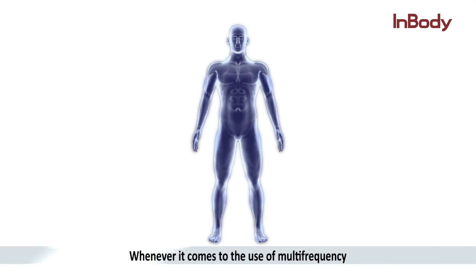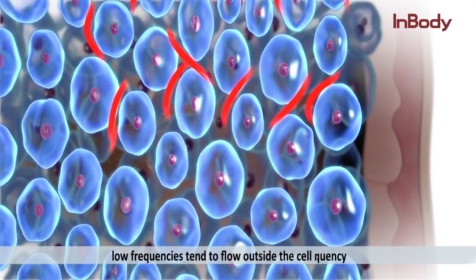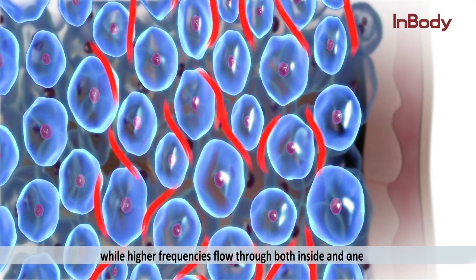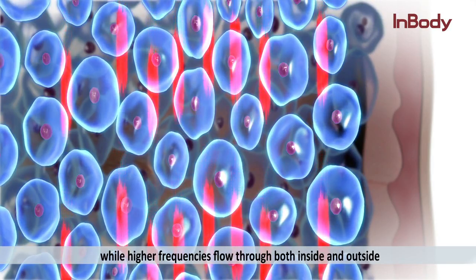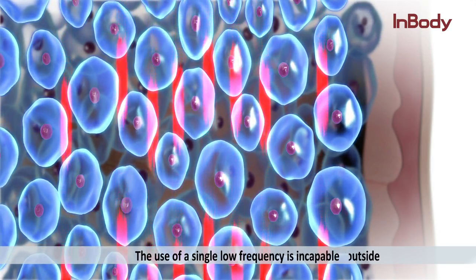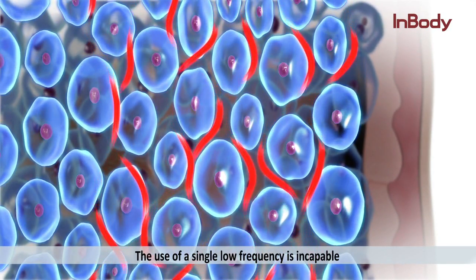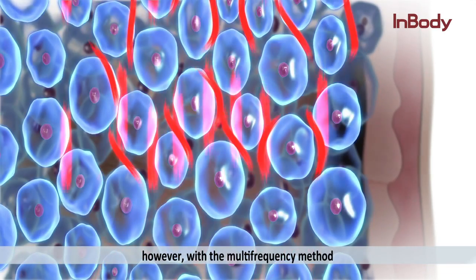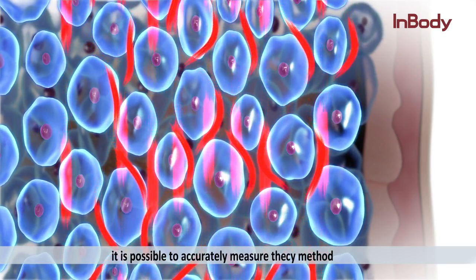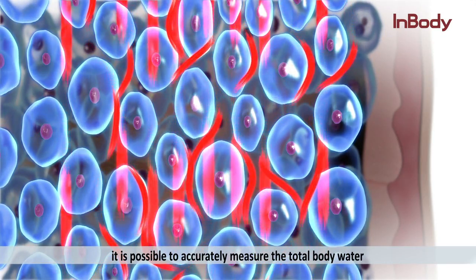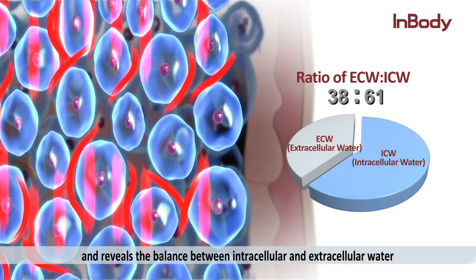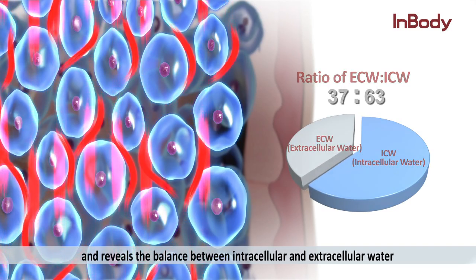When it comes to multi-frequency: low frequencies tend to flow outside the cell membrane, while higher frequencies flow through both inside and outside. The use of a single low frequency is incapable of determining the water inside the cell. However, with the multi-frequency method, it is possible to accurately measure the total body water. More importantly, this method distinguishes and reveals the balance between intracellular and extracellular water.